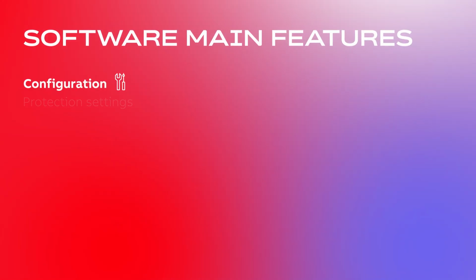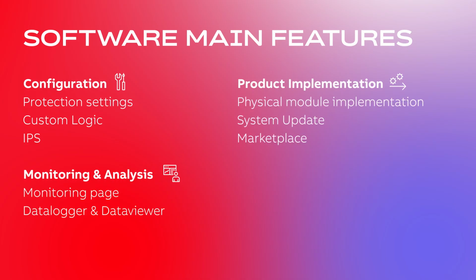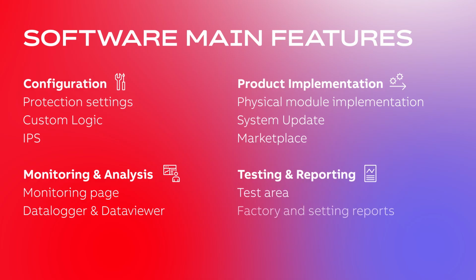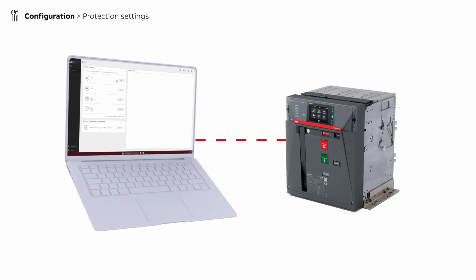Ekip Connect assists the commissioning process of the system with easy and intuitive navigation. It allows rapid access to diagnostics, immediate setting and testing of releases, complex plant configurations, and continuous monitoring on connected devices. Take advantage of the protection menu for a straightforward setting of the device releases.